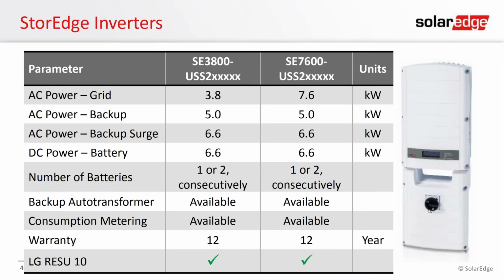All right, so here's the StorEdge inverter. So again, I said it's a 3.8 kilowatt inverter or a 7.6 kilowatt AC, and that's when it's connected to the grid. However, when both inverters are in backup mode, they can have a continuous discharge of 5 kilowatts. They also support a surge of 6.6 kilowatts. So as you can see, the 3.8 kilowatt StorEdge inverter operates like the 7.6 when it is in backup mode.